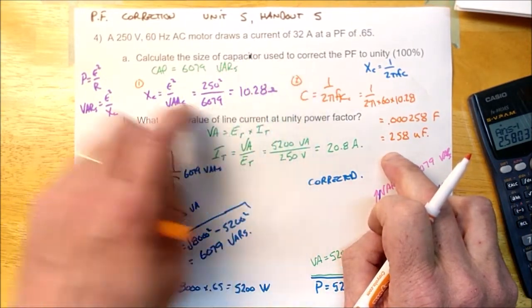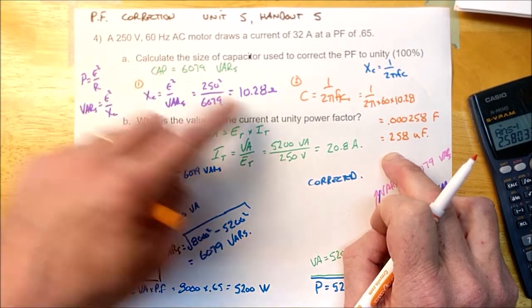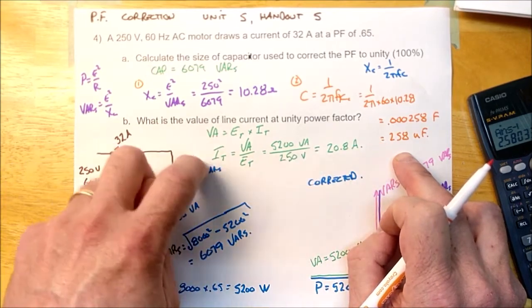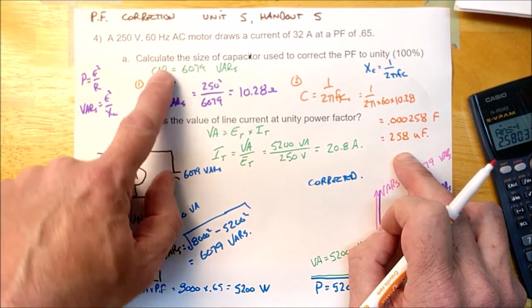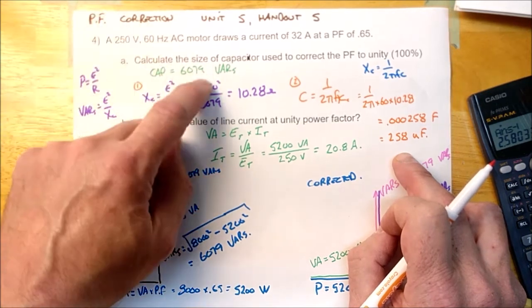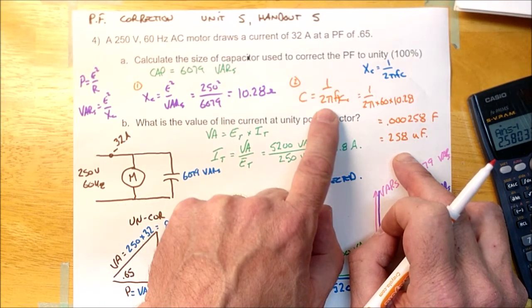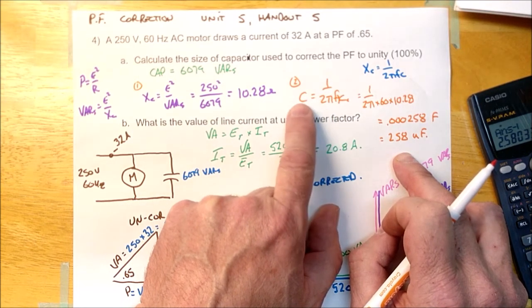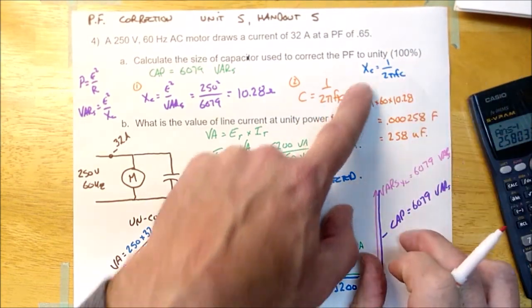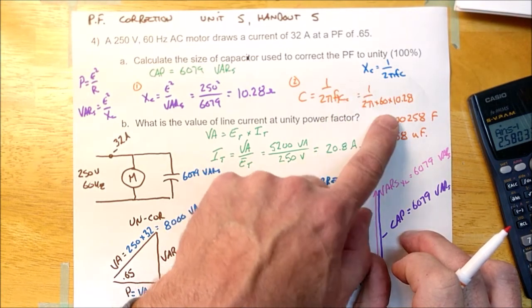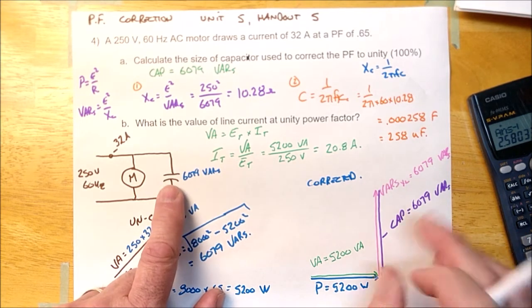So two steps. And this question doesn't even ask for it in microfarads, but some of your homework will. After you've calculated how many VARs it is, the way to convert that into farads or microfarads is to apply this formula. It's always going to look like this. XC is equal to E squared over VARs. It is the voltage squared over the VARs of the capacitor, 10.28 ohms. The next thing it's going to ask is how many farads it is. And it's this formula right here, but it's transposed for C, 1 over 2πFXC. There it is, 258 microfarads is the capacitor size.